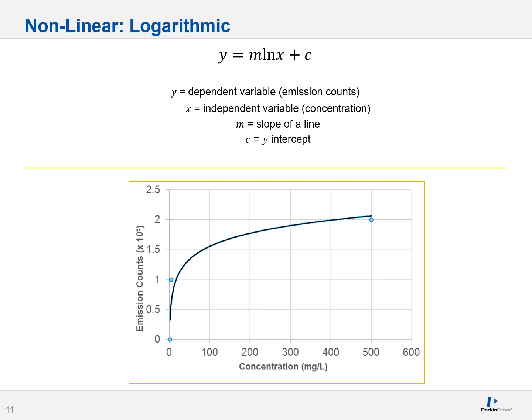Do you see the three points? Imagine I tried forcing a straight line through those points. How would I force it? How could I conceivably get a straight line that would magically hit the low, medium, and high standards? I wouldn't. You have to use a nonlinear curve. In this case, the way the points are is best represented by a logarithmic curve.